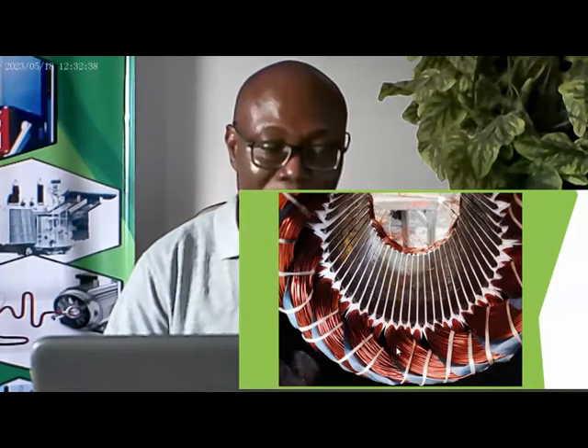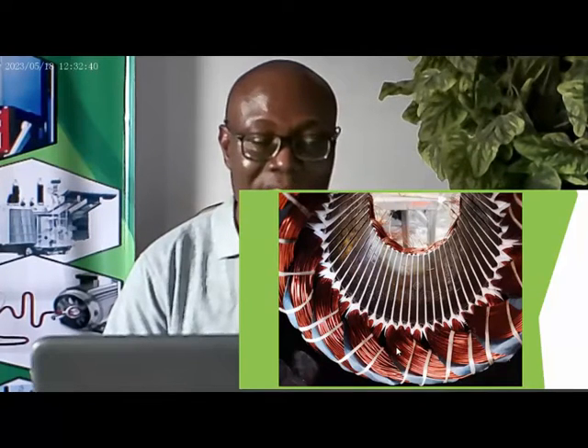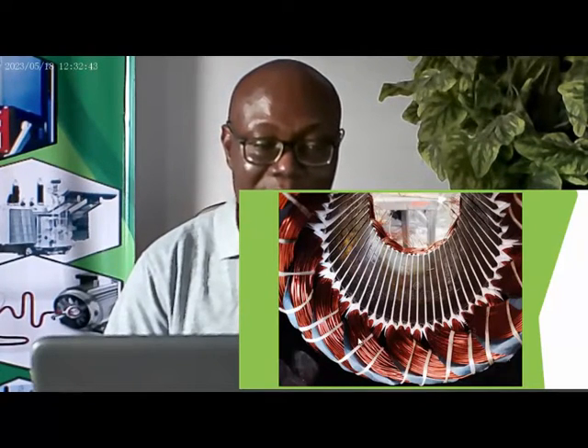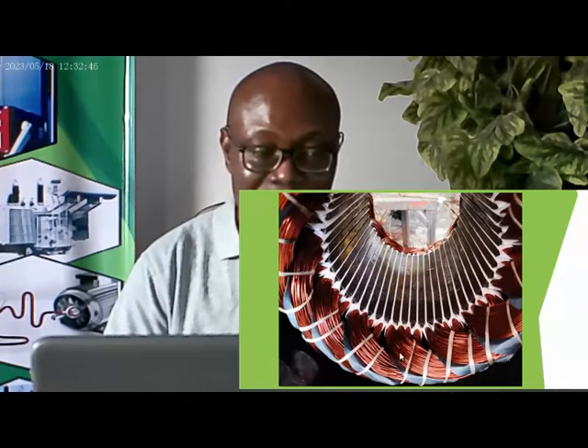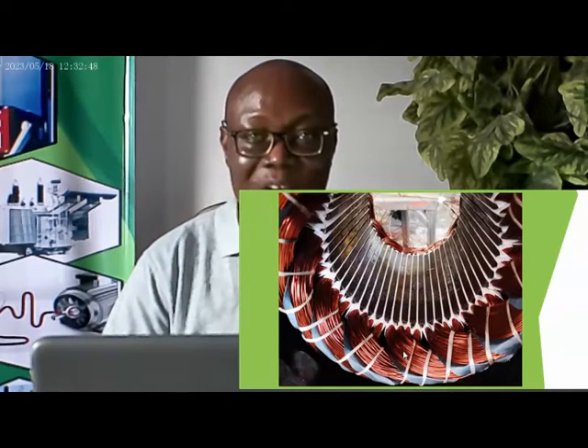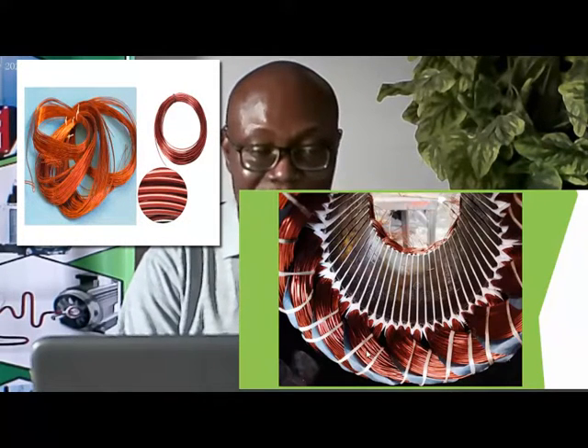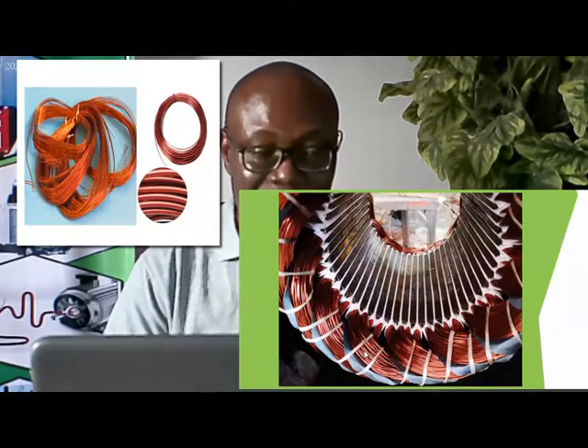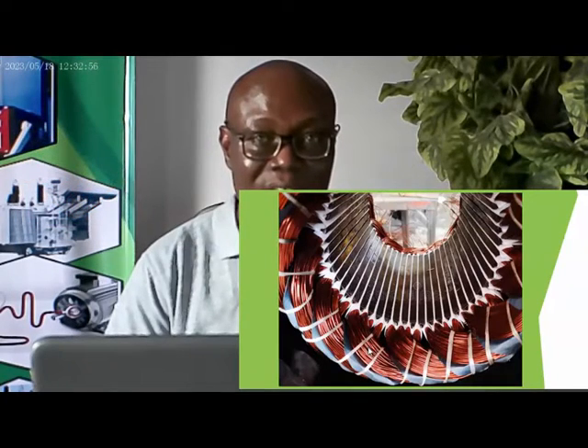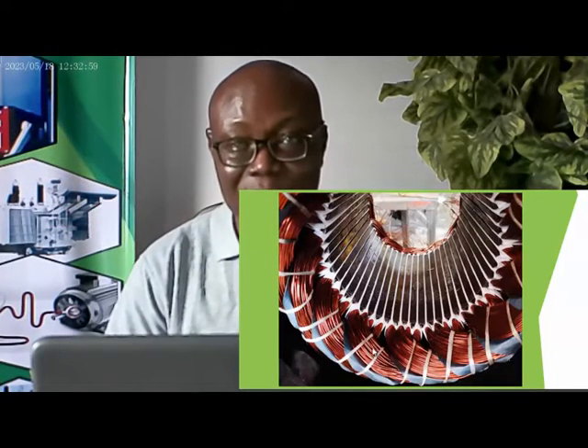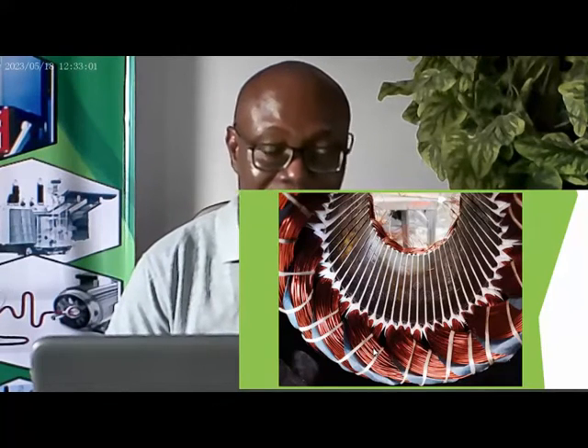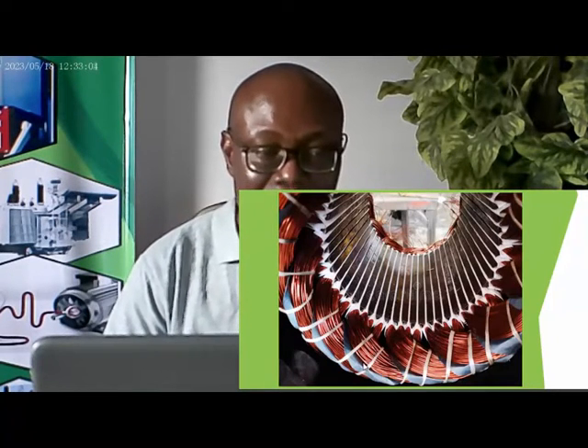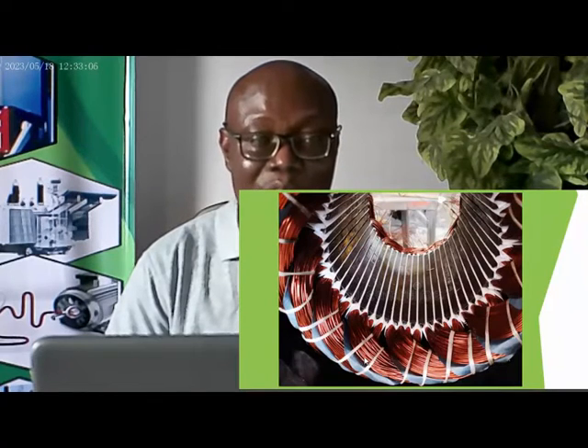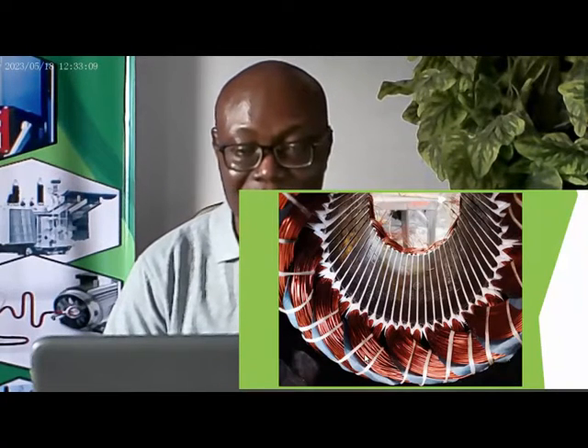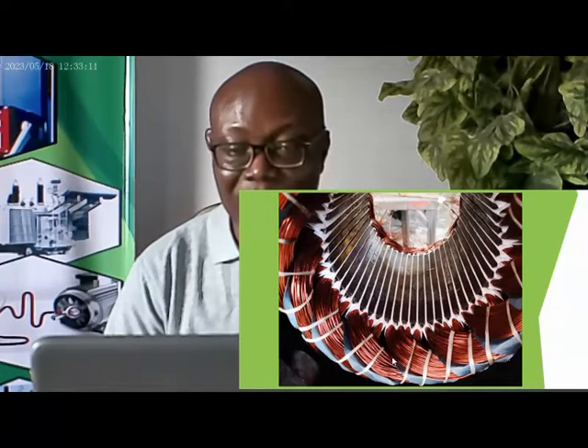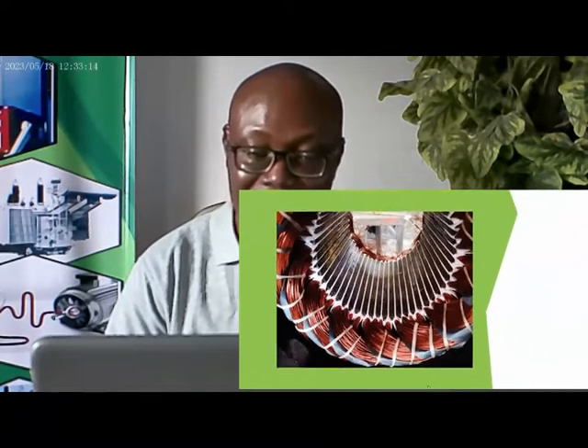Then if you look at this copper conductor, this winding wire, it is insulated. If you look at it critically, you see that it is coated with varnish. So each strand is insulated from the next strand. This will be important when we are doing winding resistance test later. So that is what you'll be testing when you are looking at the insulation resistance of the electric motor. This is the one that has been installed and tied.